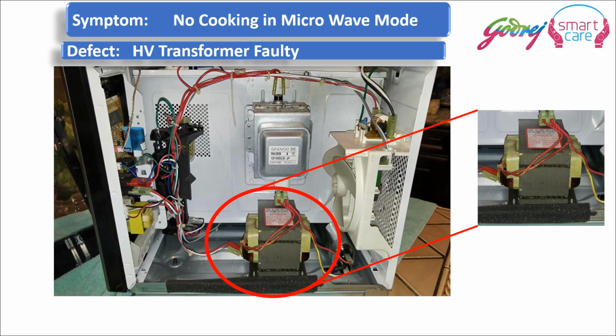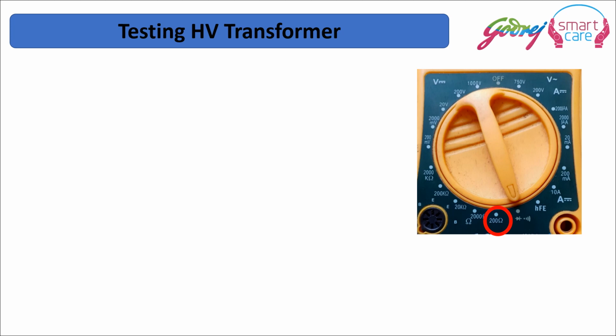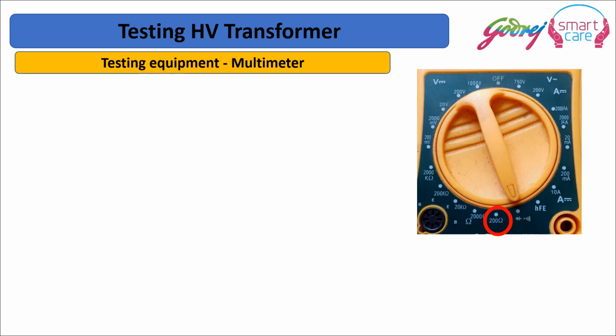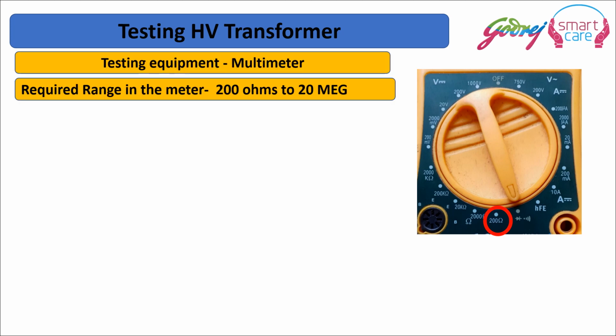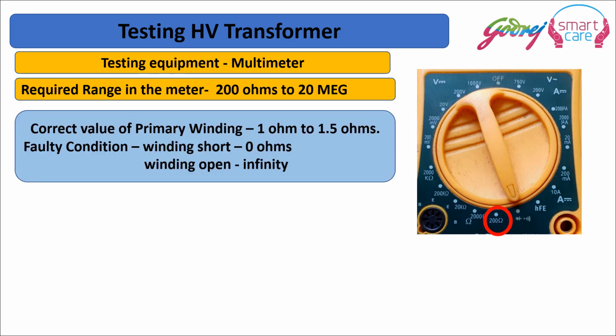How to check whether the HV transformer is faulty? For testing the HV transformer, what we need is a multimeter, and we have to check the resistance at various places on the transformer. Here is how we will do it. We check the primary windings. Across the primary winding, the resistance would be 1 ohm to 1.5 ohms. That's all. A faulty condition is if the two leads of the primary winding show 0 ohms.